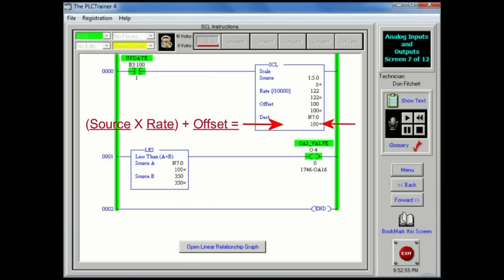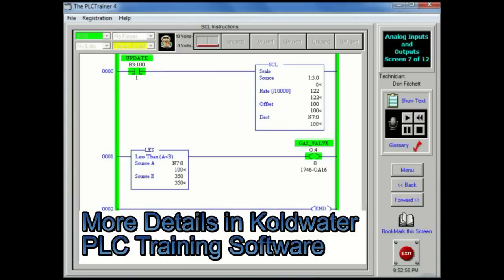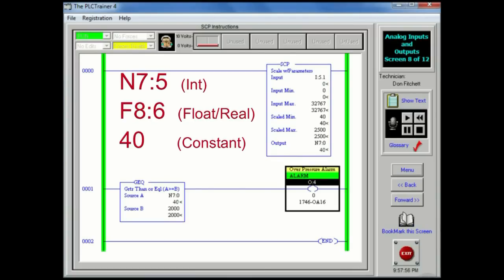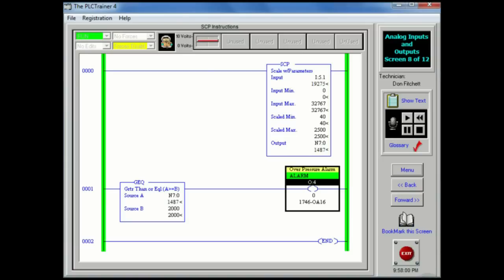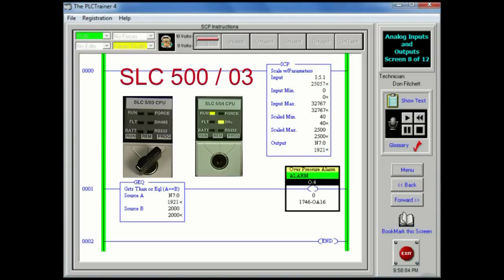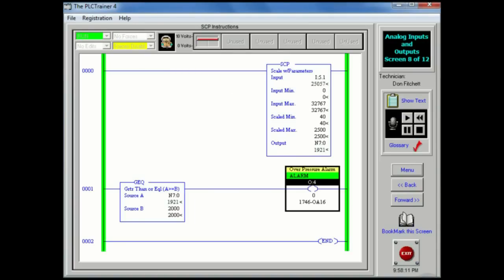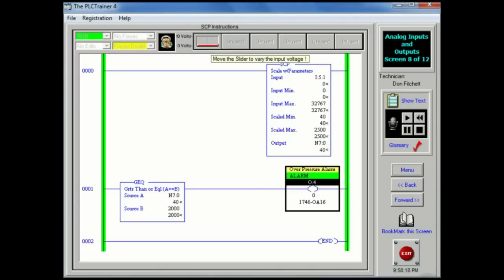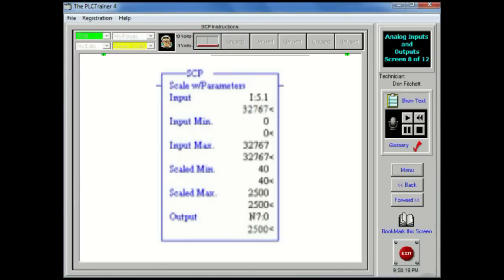The SCP or scale with parameters instruction is an output instruction that contains 6 parameters. These parameters may be integer, floating point, or immediate data values or constants. The SCP instruction is only available in SLC 5-03 processors and above, as well as MicroLogix 1200 and 1500 processors. All of the calculations needed for the SCL instructions are done by the processor when using the SCP instruction. The parameters needed by the SCP instruction are below.